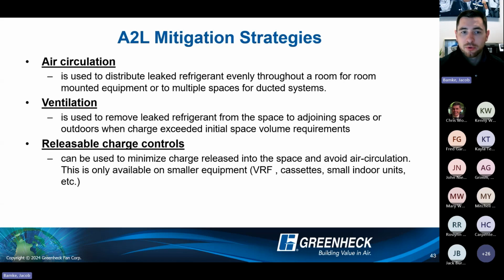Ventilation is used to remove leaked refrigerant from a space, either to adjoining spaces or outdoors, when the charge exceeds the initial space volume requirements. So if my unit's refrigerant charge is over what it could be for a certain space, and I don't have ducted systems that I can diffuse or distribute this to evenly, you might have to design ventilation in the space itself to take care of any leaks.